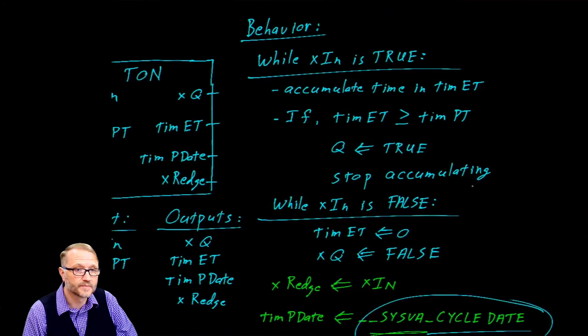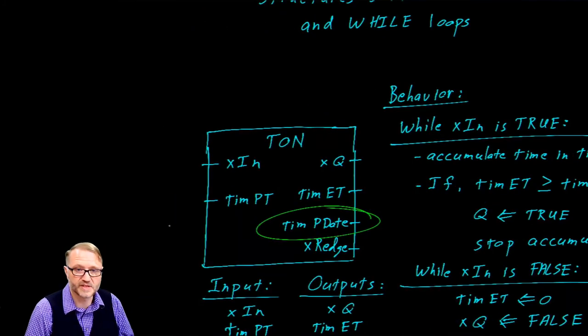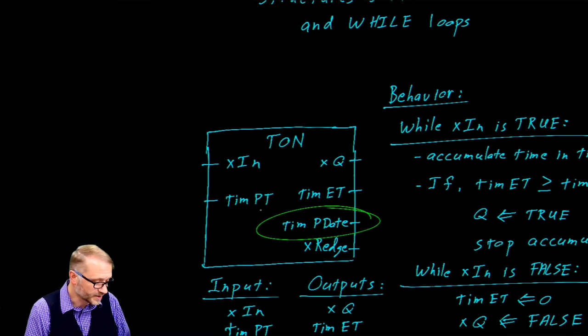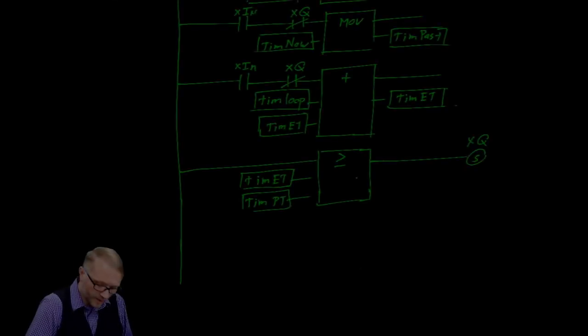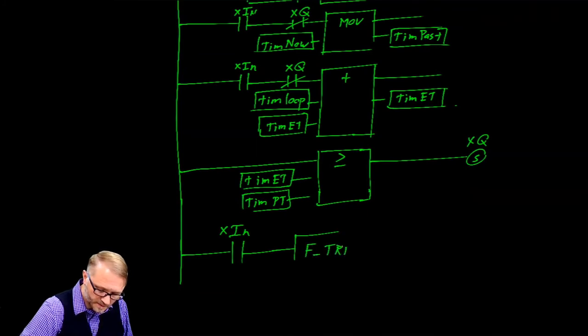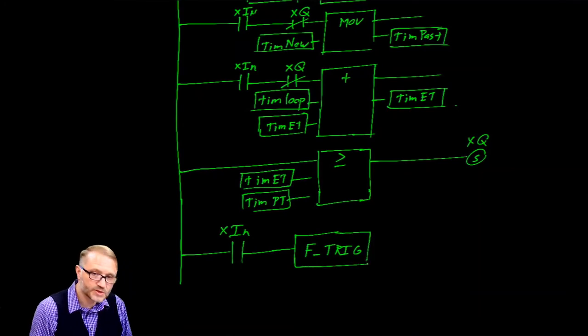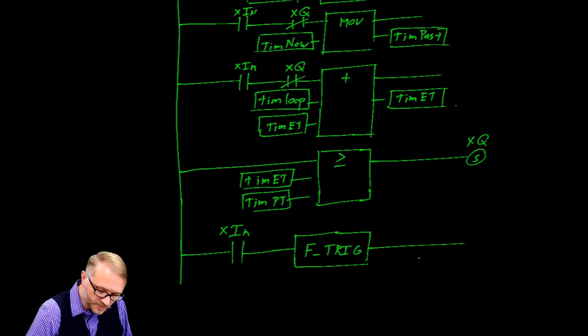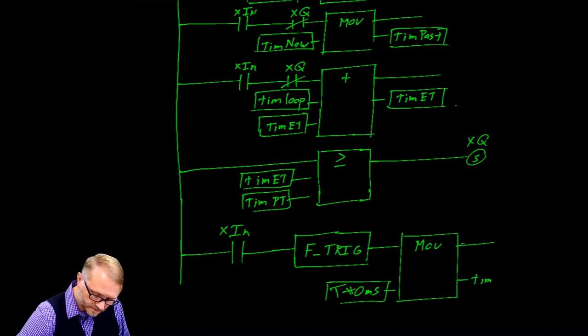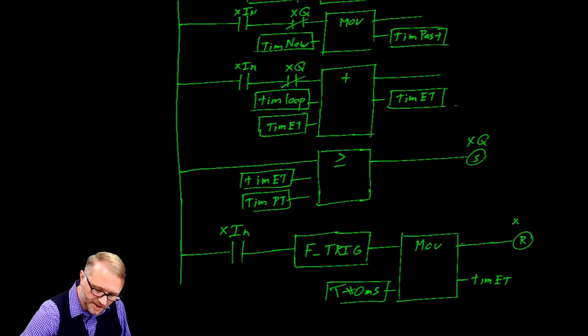That's actually this variable called the previous date — we stop updating it when elapsed time is greater than or equal to program time. One more rung and this is complete. We need to look at the boolean input — in particular, the falling edge. So a falling edge trigger. There are two things we need to do: first, move time zero milliseconds into elapsed time, and also reset the latch on Q.